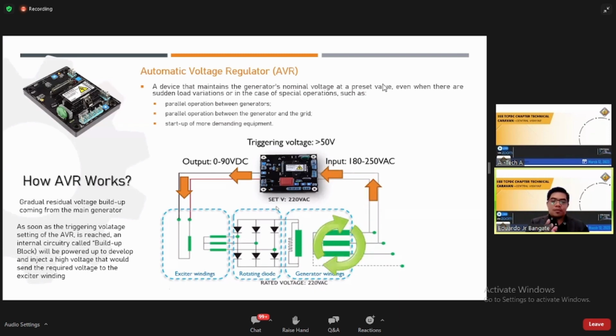Now, how will it do its real function? It is called an automatic voltage regulator, so it has to act automatically to regulate the voltage. When you put the load, it means that you are putting a stress on the generator. It means that the shaft of the engine will find it harder to turn the alternator. In this case, the voltage will go down. And this is the function. As soon as our AVR senses that the voltage goes down below its required level, it will inject more voltage into the exciter to raise the voltage and maintain the output voltage level of our generator. I hope everyone understands that one.